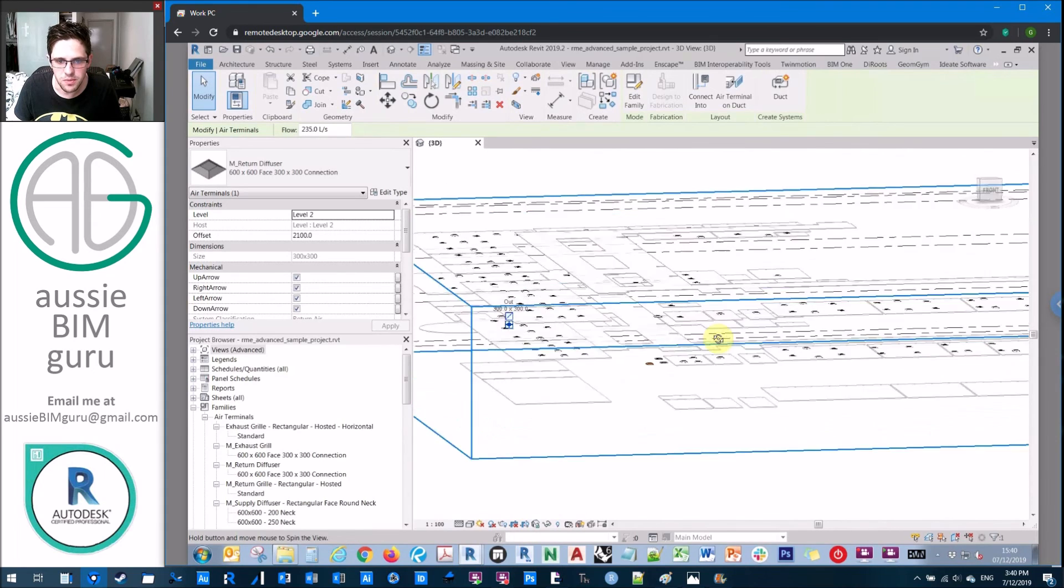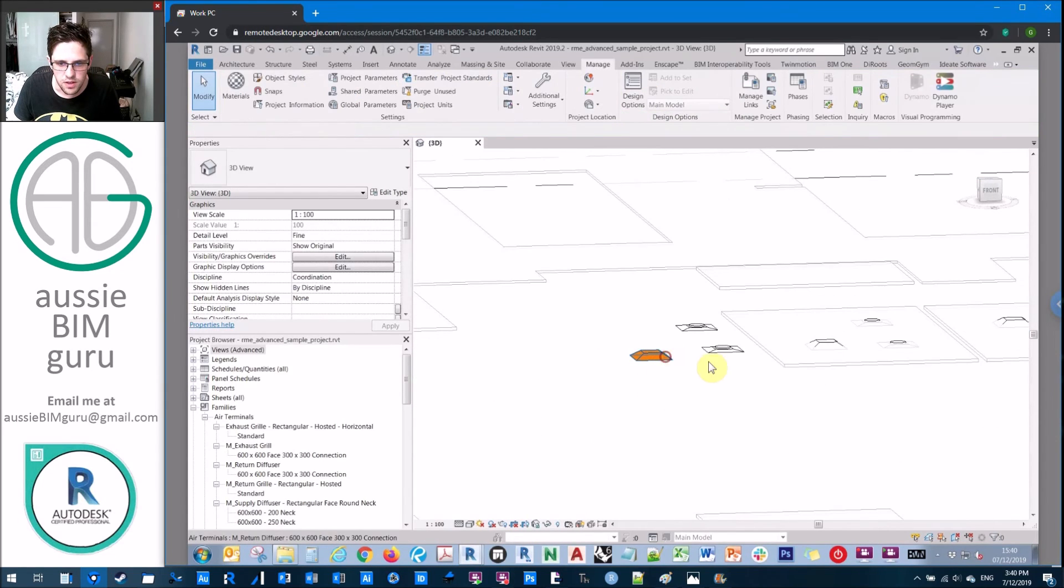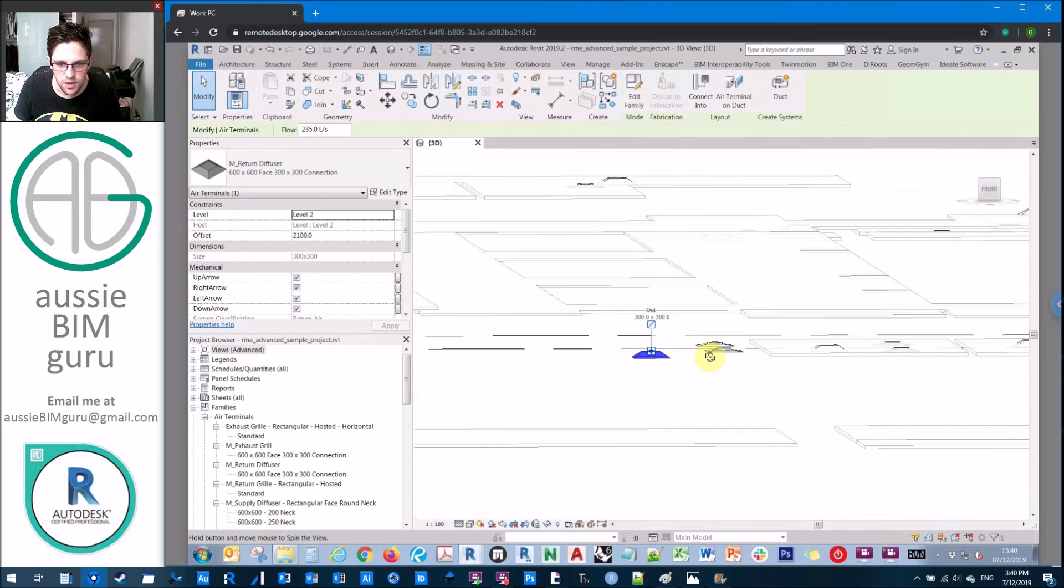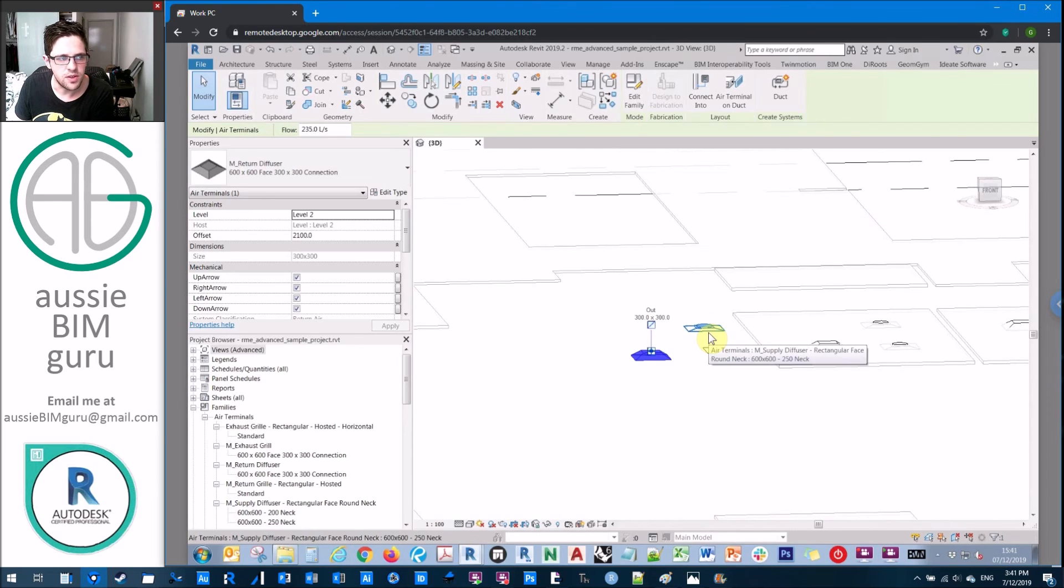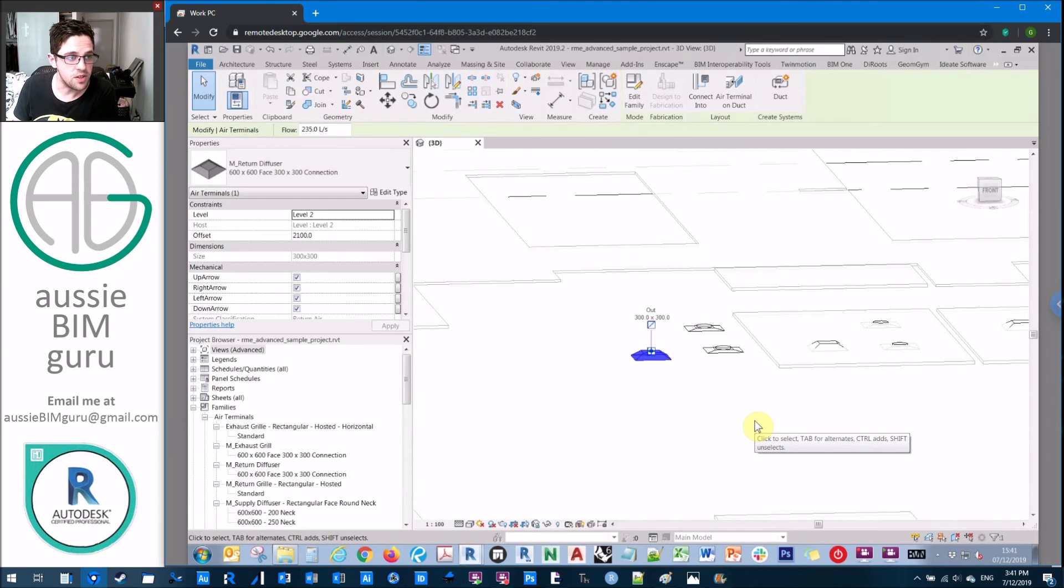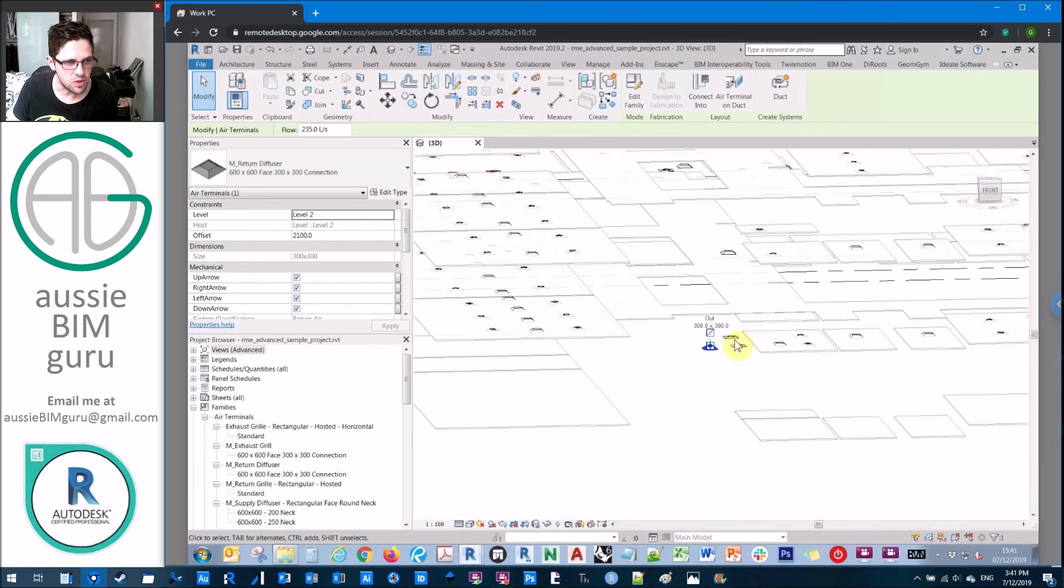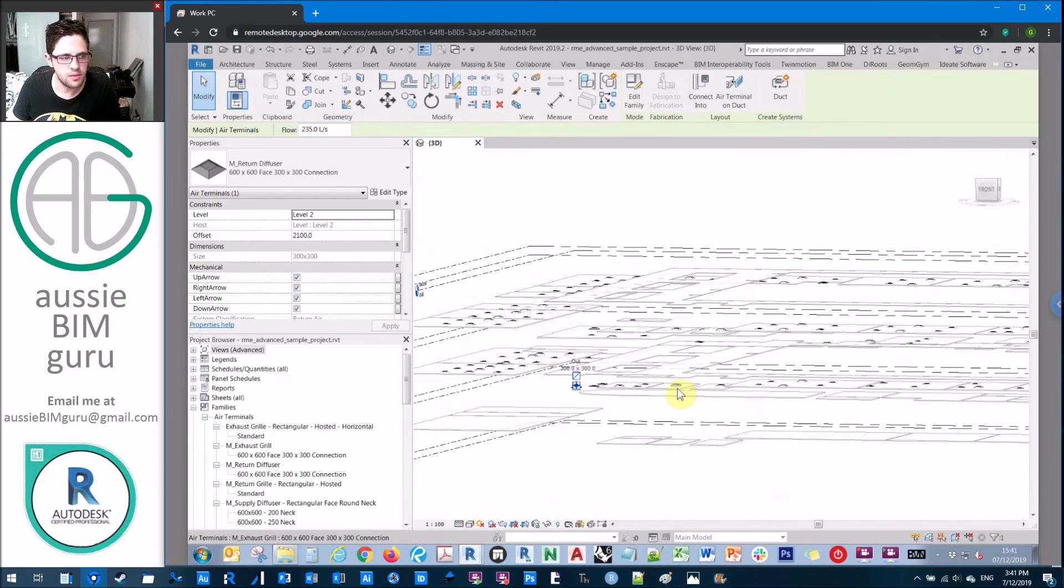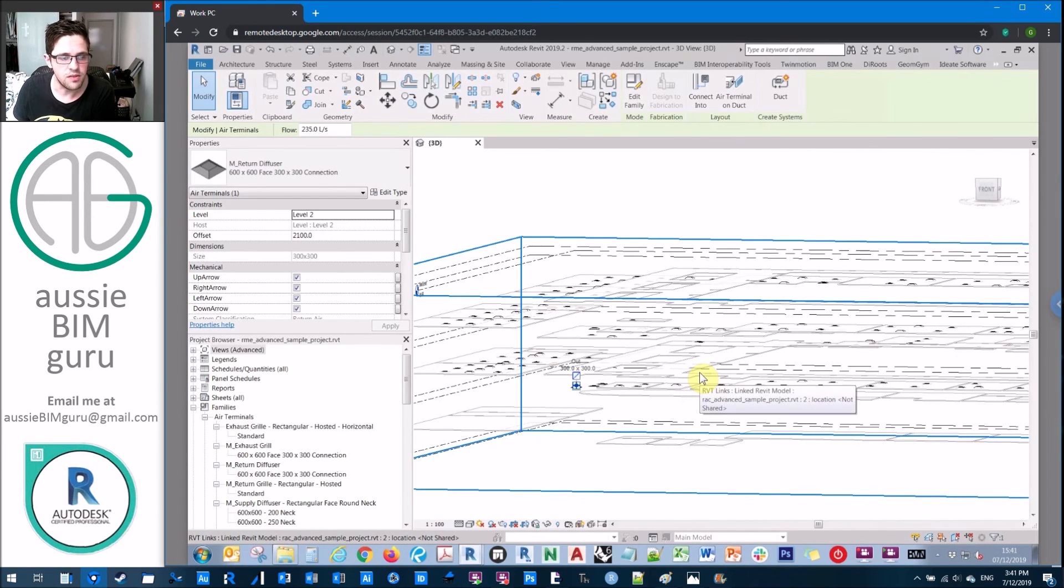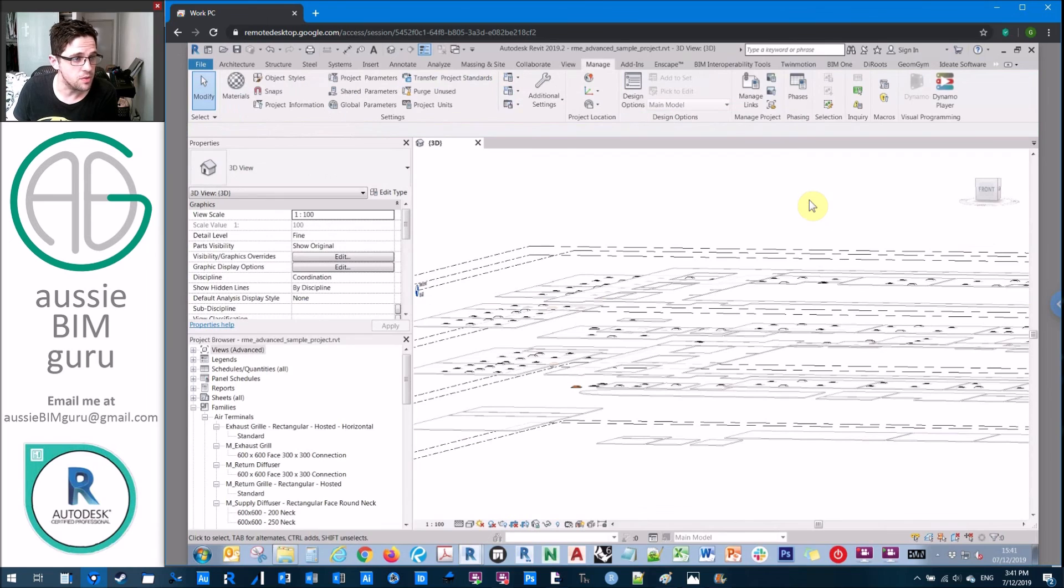We can obviously see other ones here as well. You can see that even though there's no ceiling in this room, it actually reached out and found the nearest adjacent ceiling. So sometimes that might not be the most ideal workflow. You might sometimes want to instead intersect a cylinder moving directly up and down from the center of the terminal. That might be a better workflow so you're only considering the vertical intersections instead. But a sphere is just a really quick and sort of dirty approach, I guess, to forming an intersection. But there you go. So a really interesting workflow. And I think there's a lot of potential to improve on it. So hopefully it gives you some ideas of how you can develop your own workflow. And thanks again, Rajesh for telling me about the workflow.